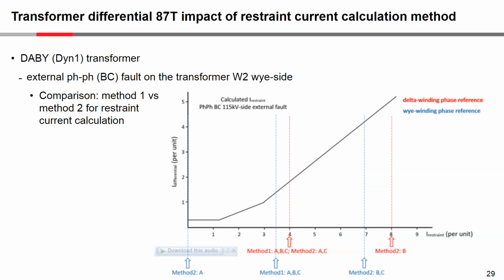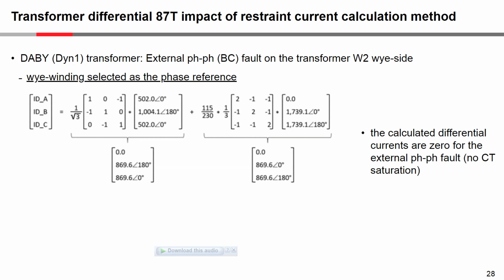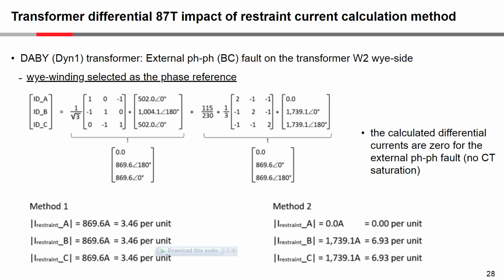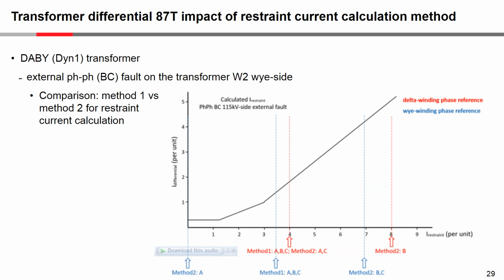If we go back and look here, when we had the Y winding as the phase reference, you can see that for method 1, all 3 phases would be calculated the same. And for method 2, we would have 0 for phase A, and phases B and C would be the same. So if we come here, you can see that for method 1 we would be at 3.4 something for ABC. We were just under 7 for method 2 B and C, but we were 0 for method 2 A.